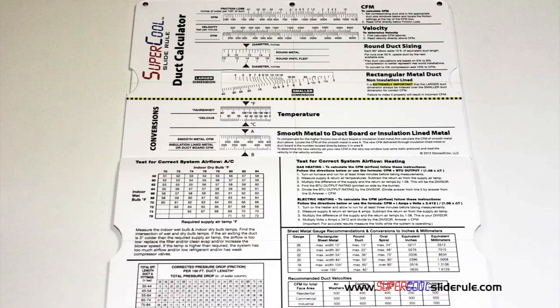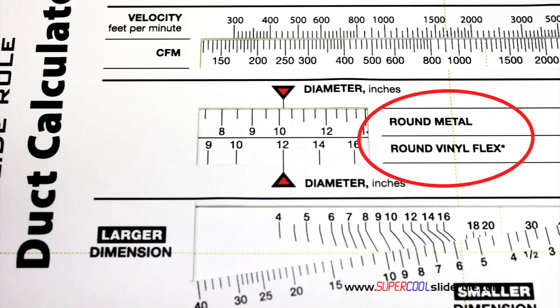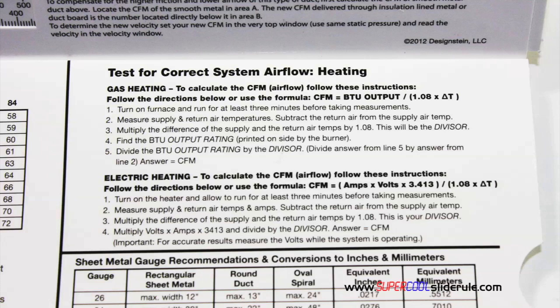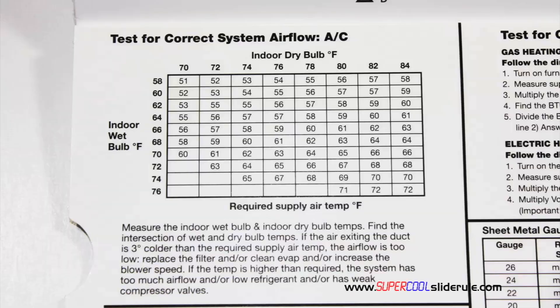Inside is packed with even more information. It performs sizing of both metal and flexible duct. It has the only direct reading conversion from smooth metal to insulated liner metal we've ever seen. The majority of technicians have never been taught that if the insulation is on the inside of the ductwork, you cannot size it with a regular duct calculator. It has step-by-step directions for determining airflow through a gas furnace, electric furnace, or an air conditioning unit.